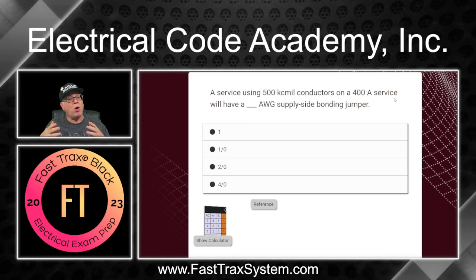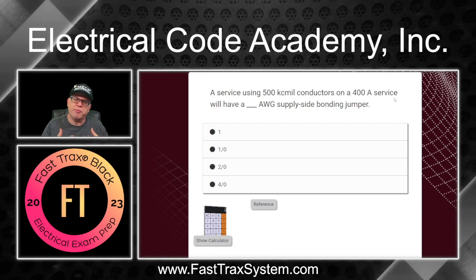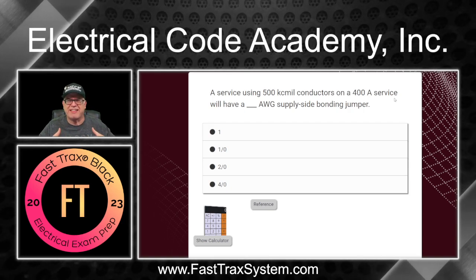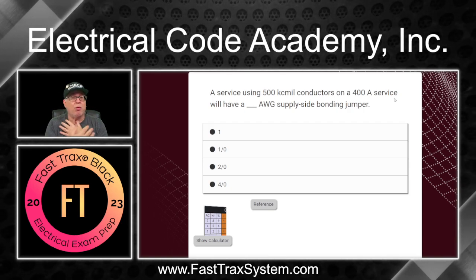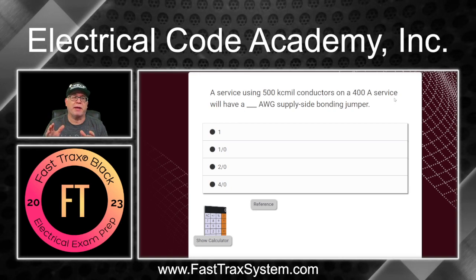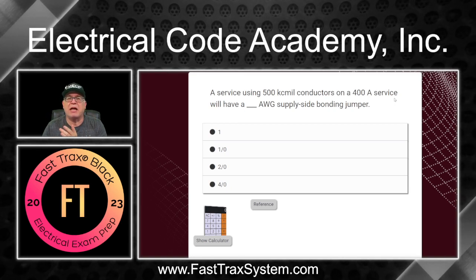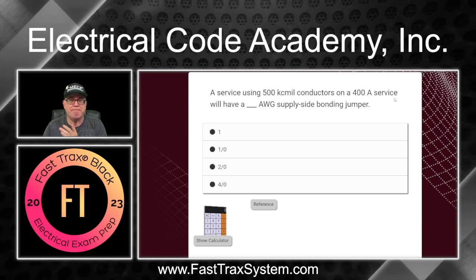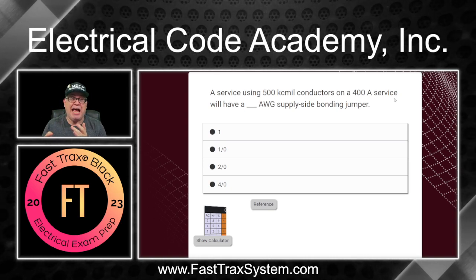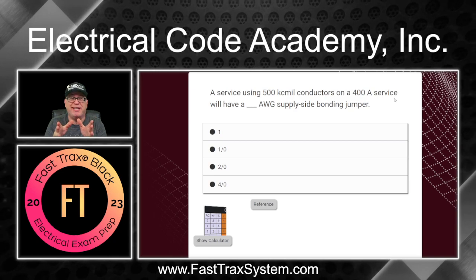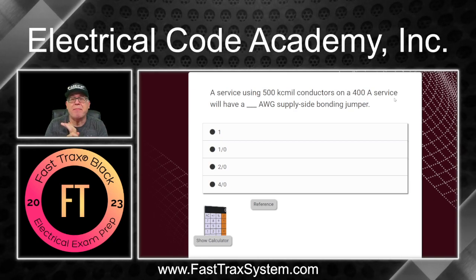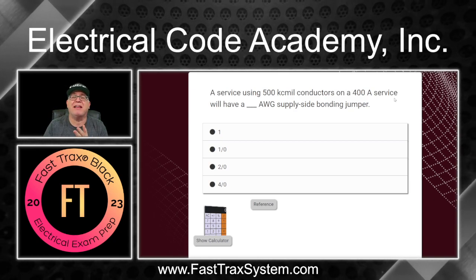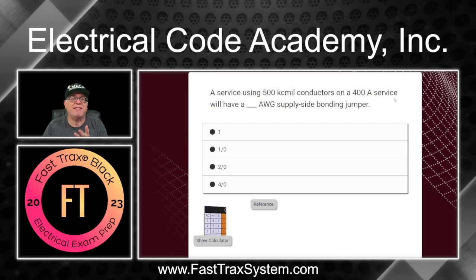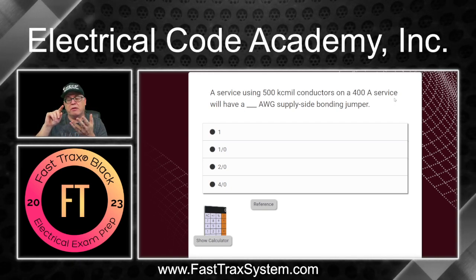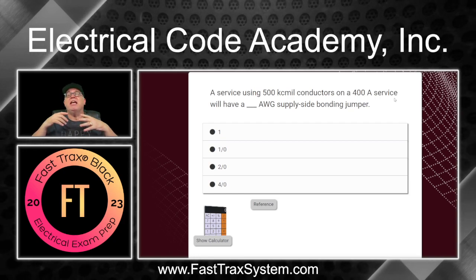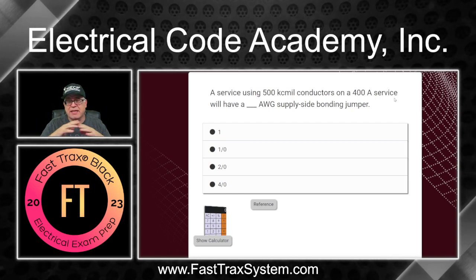And then one of the tables that was derived from 250.66, but it stands on its own, is probably one of my favorite tables, being I serve on Code-Making Panel 5, is 250.102(C). I think (C)(1) actually, but that gets you where you need to be. That table is amazing because it determines the minimum sizing for the grounded conductors, supply side bonding jumpers, system bonding jumpers. It is an amazing table.